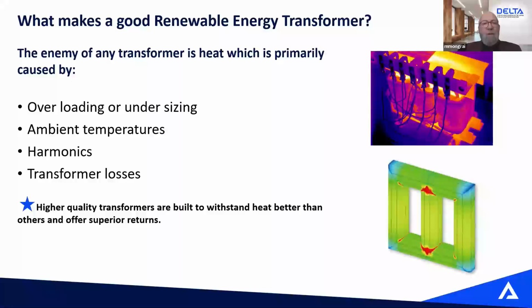As you all may be aware, the worst enemy of a transformer is heat. What will cause a transformer to eventually fail is heat, which will slowly, I would say, degrade the strength of the dielectric insulation system that builds your transformer. So our transformers are built with a 220 degrees Celsius insulation system. So again, the more the transformer runs warm, the more you run closer to that point, the shorter lifetime you'll get out of your transformer. So there are ways to have a transformer that's going to operate at lower temperature. One is the size of the transformer, the load of the transformer, the level of harmonics.